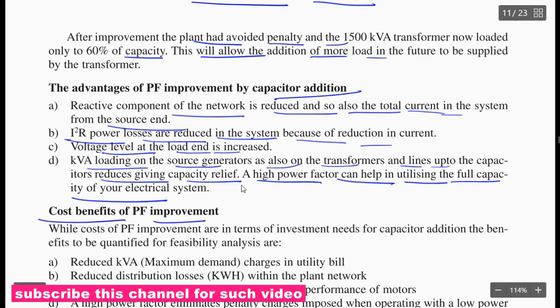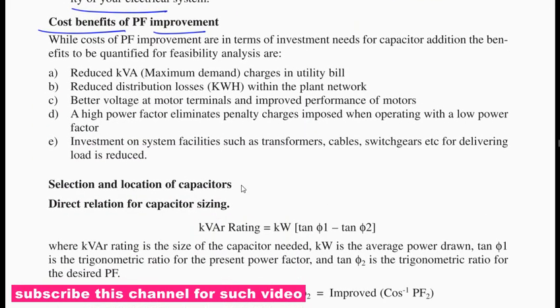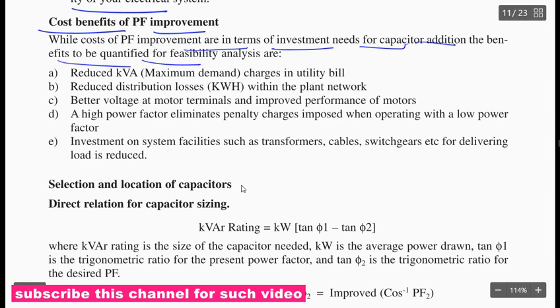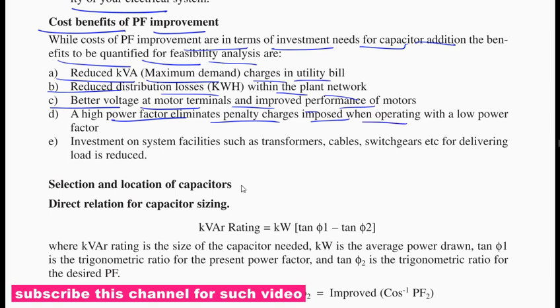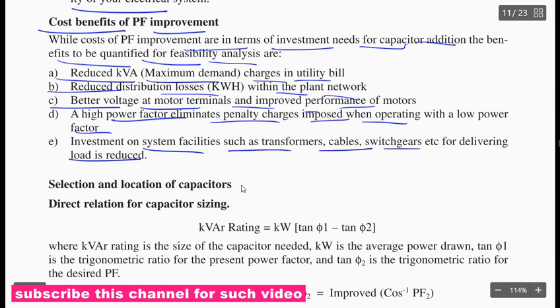Cost benefit of power factor improvement, let us see. What is the cost benefit? While the costs of power factor improvement are in terms of the investment needed for the capacitor addition, the benefits have to be quantified for the feasibility analysis. Reduced kVA maximum demand charges, reduced distribution losses within the plant network by the utility, better voltage at motor terminals and improved performance of motors. A high power factor eliminates the penalty charge imposed when operating with a low power factor. Investment on system facilities such as transformers, cables, switchgears, etc. for delivering load is reduced.